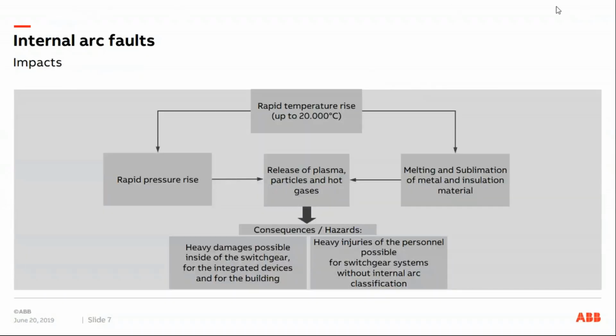So, as we've just mentioned, the effects: an internal arc fault is characterized by a rapid temperature rise up to 20,000 Celsius. This causes a chain reaction of other hazardous impacts. Users would like to prevent system components from being destroyed. And of course, the absolute protection of the personnel is by far the most important concern during an arc fault.